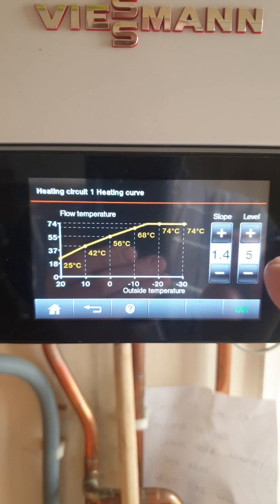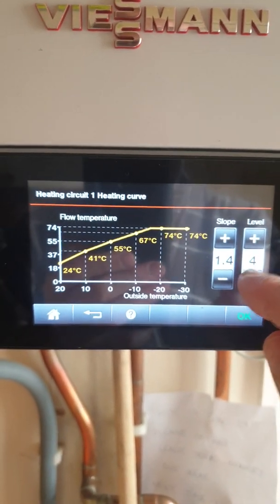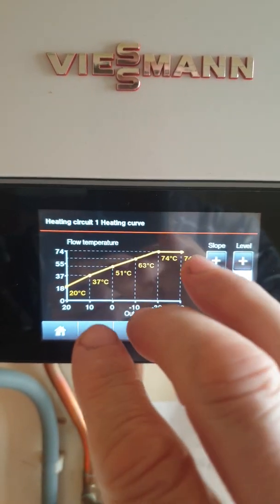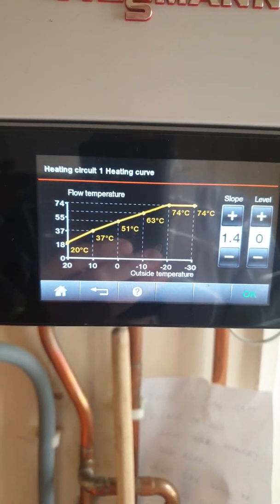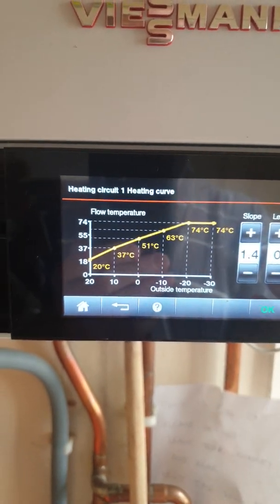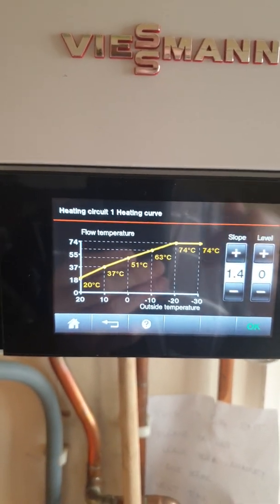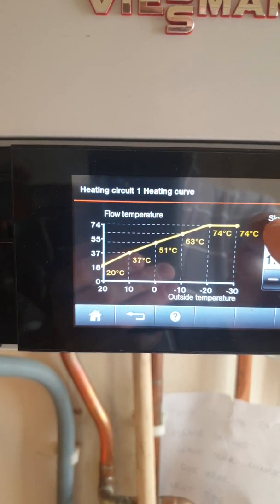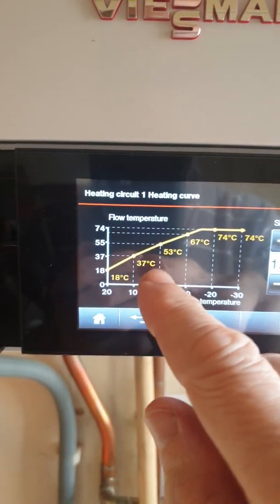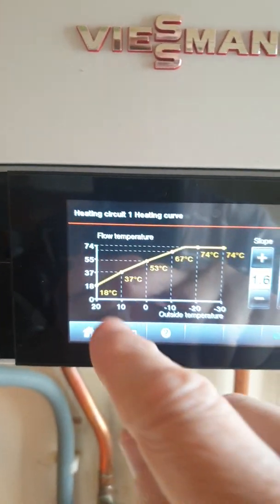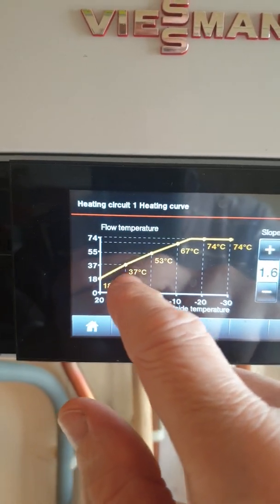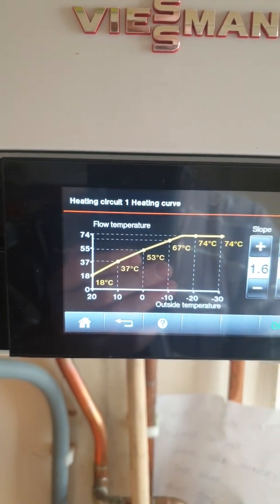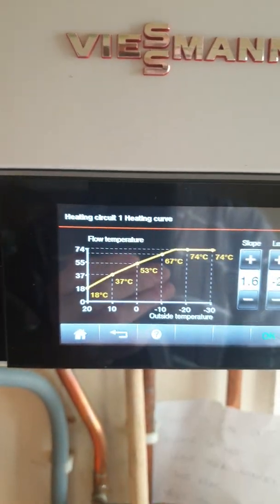You might want to create a sort of hybrid curve. For example, as humidity changes in the summertime — as we're coming up to warmer weather — we don't need the same internal temperatures. We can drop the internal temperature slightly to get the same level of comfort. So what we could do is raise the slope and then reduce the level. In effect, what this is doing is kind of steepening up our curve, so that as we approach the summertime period, we're going to drop off a little bit on our temperature — or conversely, increase our temperature as we get to the colder period.